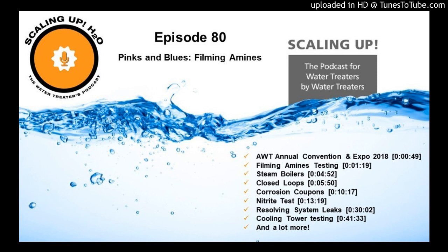So we did all of this through a filter feeder, and I'm a firm believer that if you do not have a filter on your closed loop system, you are not getting the job done. Folks, our job is to make sure that our heat transfer surfaces are as clean as possible. And if you don't have a filter in there, there is no way that you are getting that as clean as it needs to be. So that's just my little soapbox for that. Put a filter on all of your closed loops.